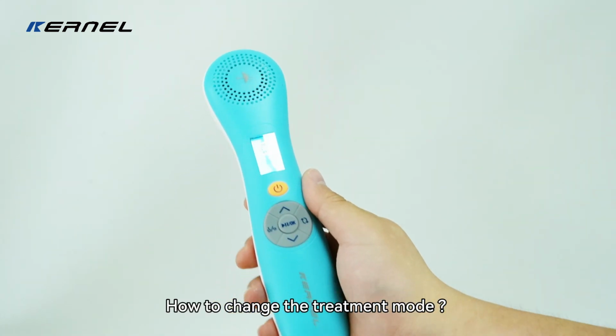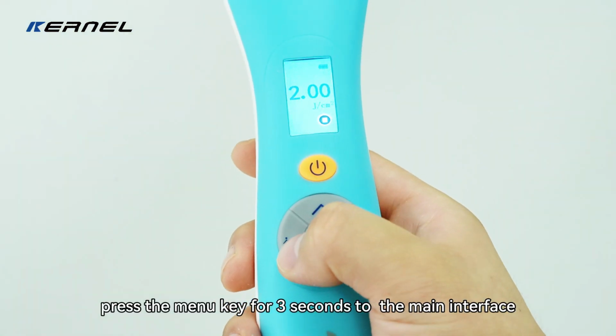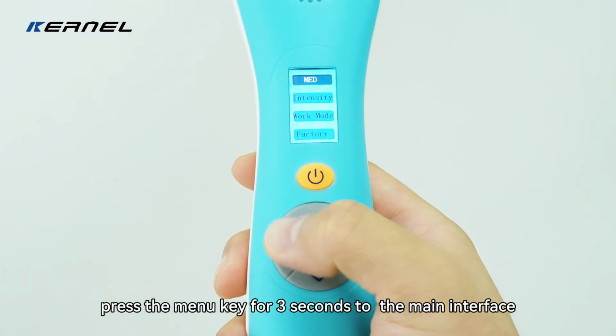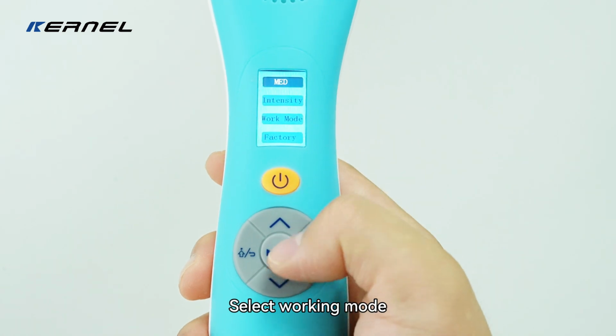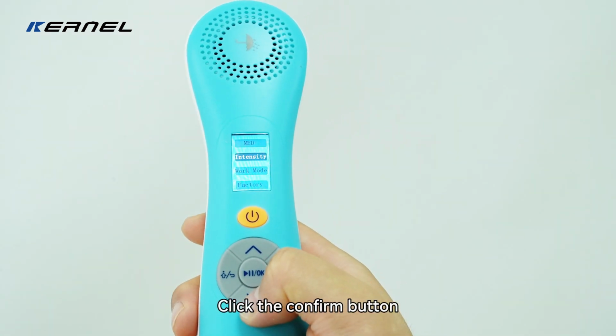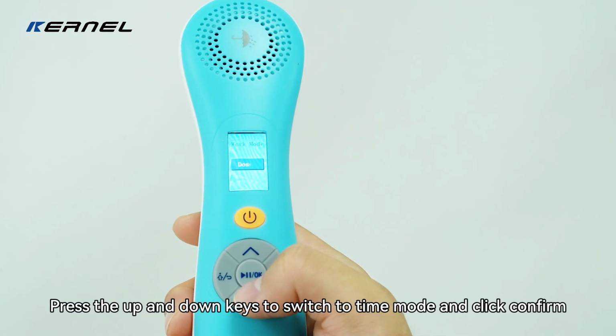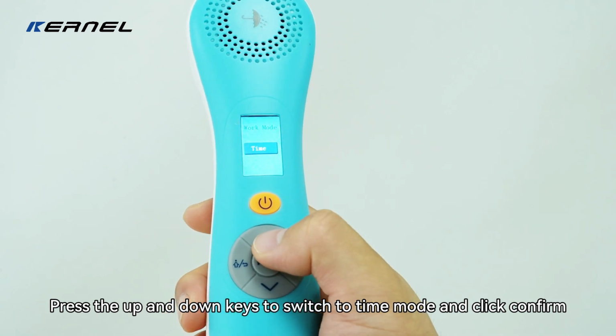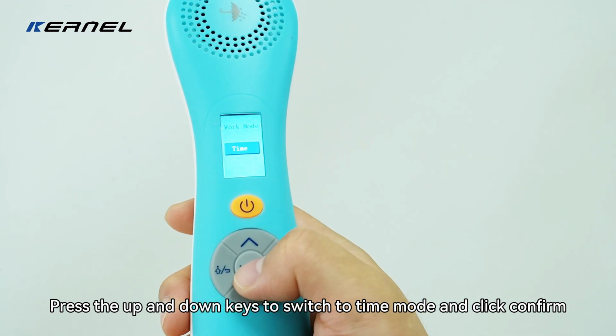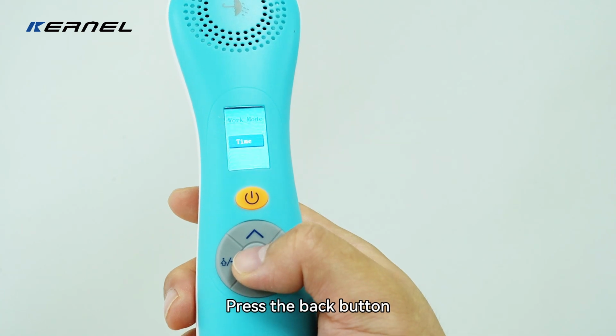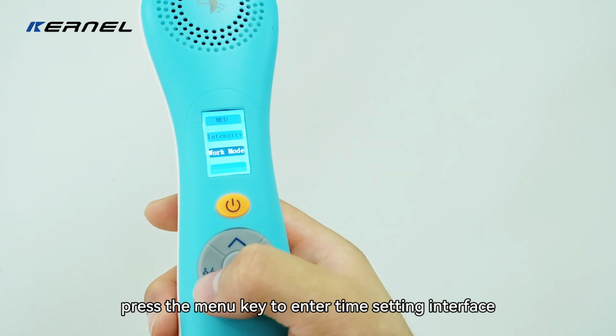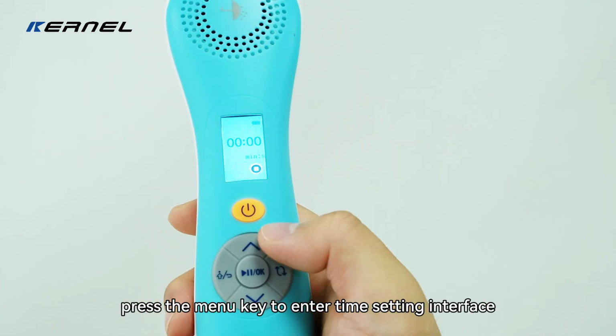How to change the treatment mode. Press the menu key for 3 seconds to the main interface. Select working mode. Click the confirm button. Press the up and down keys to switch to time mode and click confirm. Press the back button. Press the menu key to enter the time settings interface.